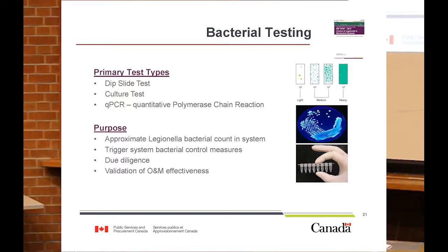And the purposes of our bacterial testing requirements are to approximate the Legionella bacteria count in our systems, trigger any necessary bacterial control measures, and provide due diligence and validation on the effectiveness of our operation and maintenance activities in actually controlling the growth of Legionella. Again, think back to that triangle. The bacterial growth side is what we're trying to attack. So here, this is really the validation step.